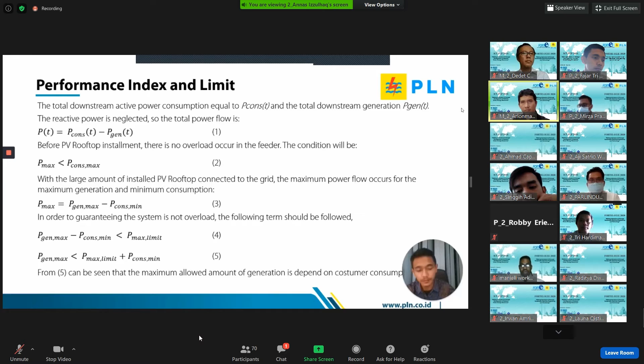So for the study case, we observe the Putri Betung feeder that is located in Gayo Lues, Aceh. This feeder is operated radially and uses 3 phase overhead lines at 20 kilovolt voltage. It also uses all aluminum alloy conductor with a size of 70 millimeter square. The feeder is 51.58 kilometer circuit length.